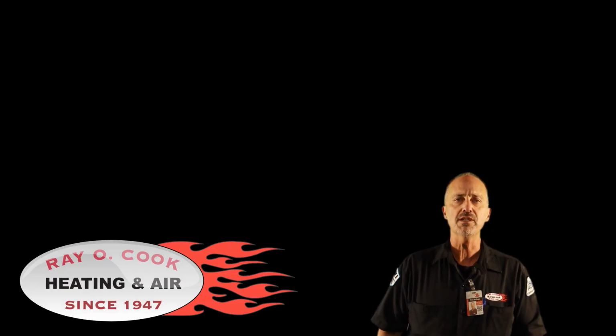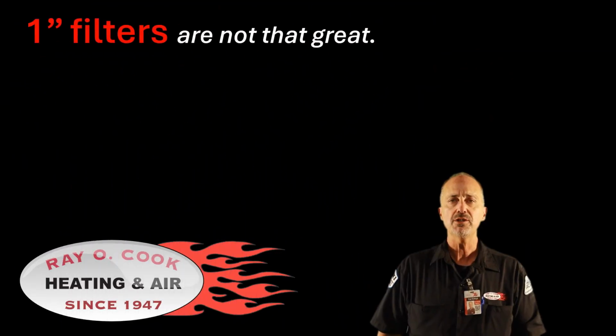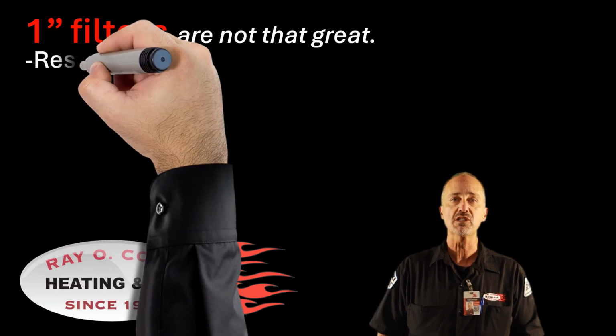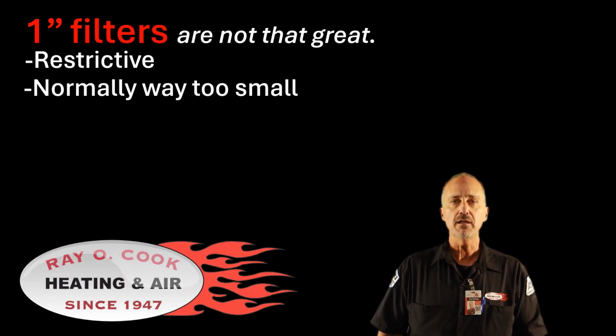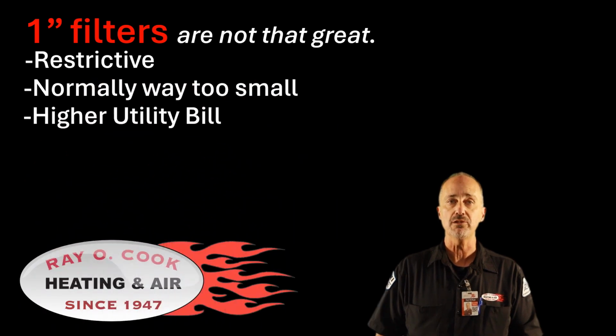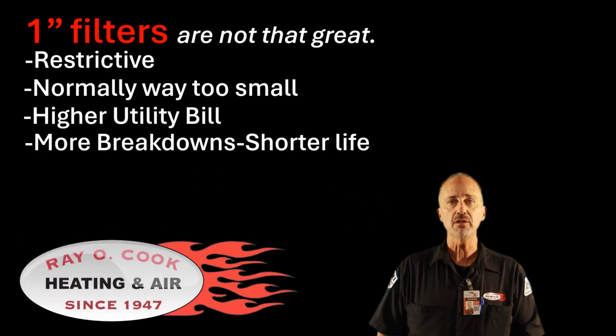So let's break down all of this into a few key points. First, if you currently have 1-inch filters installed in your system, chances are you are already near, at, or over the restriction rate your system can handle in order to provide the volume of air that your system needs. It is a simple fact that most air filter grills are too small, way too small in our area. If you are lowering your airflow with a restrictive filter, you are lowering your equipment efficiency and probably raising your utility bill. You are also causing your system to work harder, a lot harder. This can only increase the likelihood of breakdowns and shorten your equipment lifespan. In most cases, 1-inch filters need to be changed at least once every 2 months or sooner because of their low dust holding capabilities.